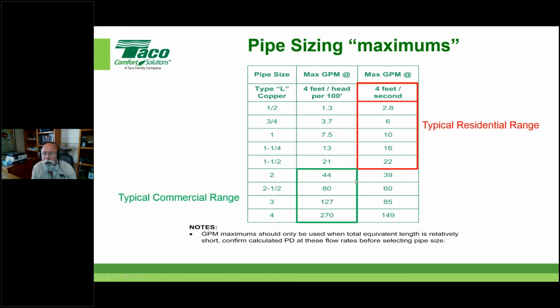So notice one thing that's significant about these maximums: right where the colors change here from green to red, residential goes to commercial, it also flip-flops in the amount. Notice this column gives you more flow than this column until you get to 2-inch, and then this column gives you more flow capacity than this column does. So you guys that are out there doing work that kind of goes into commercial, just remember where you can flip-flop to your advantage. Use what's within our industry's acceptance to your advantage. When you remember things like this, it helps out quite a bit.